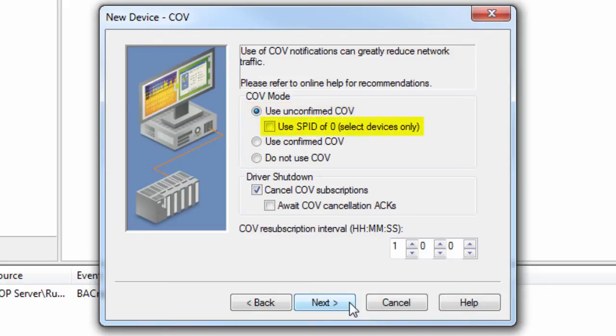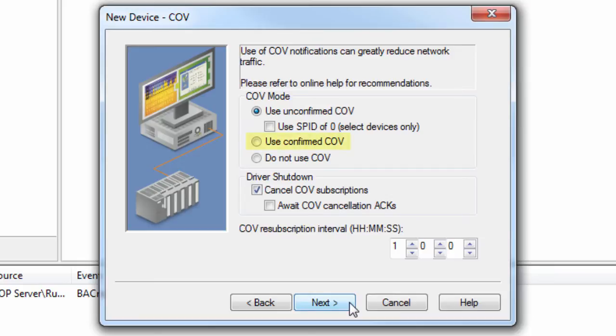Some devices require the subscriber process identifier for all COV items to be zero. If this is not the case, this setting should be left unchecked. When unchecked, a unique identifier will be used for each subscription. Use confirmed COV tells the driver to acknowledge each received COV notification.